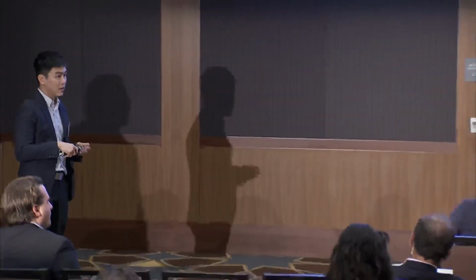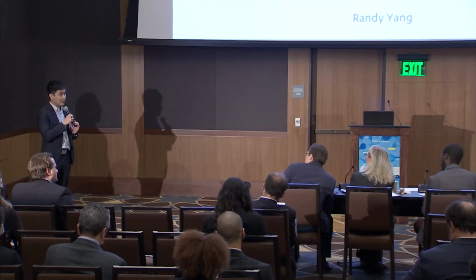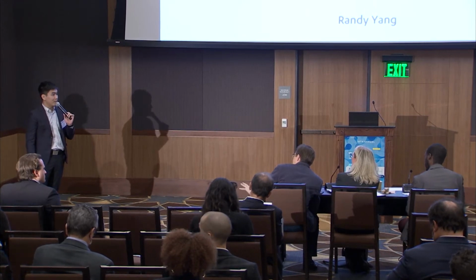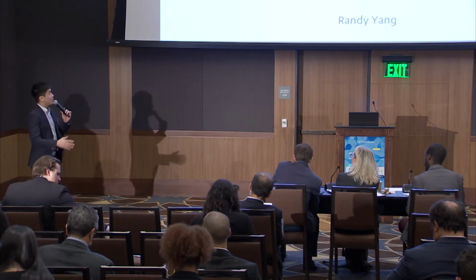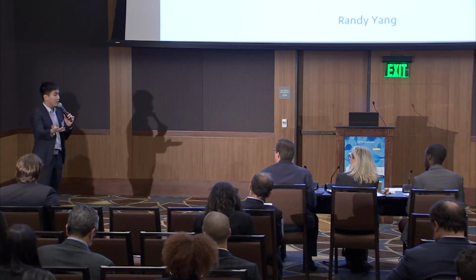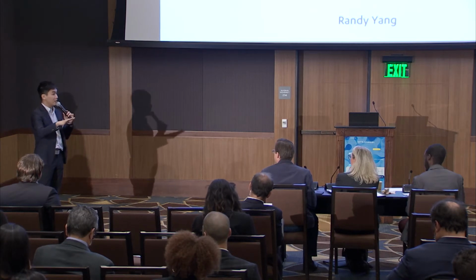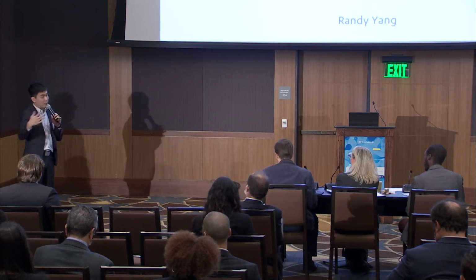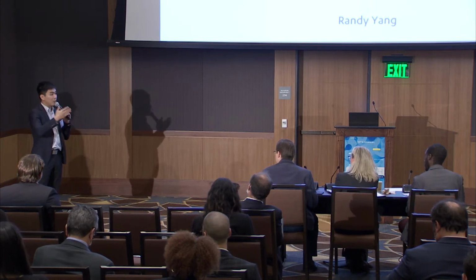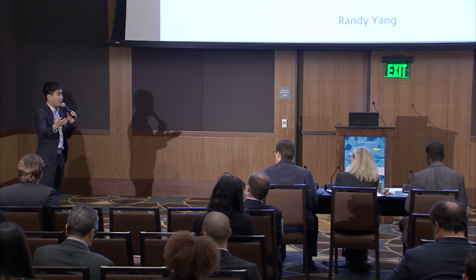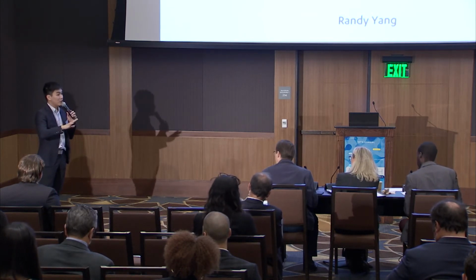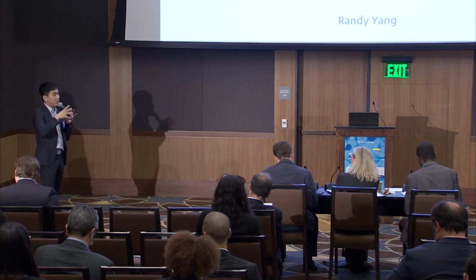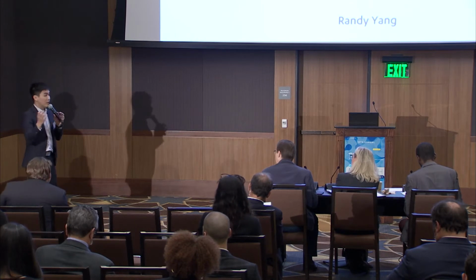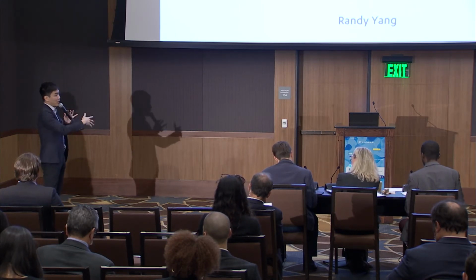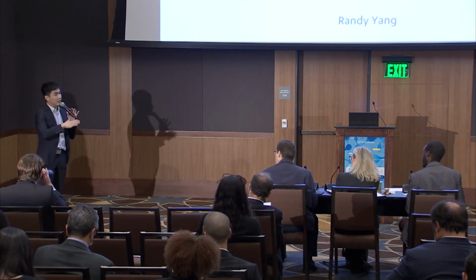Thank you. And for an owner of an MRI machine, what's the cost and the barriers to implementing your coil and replacing it? Right. The standard cost of a brand coil that is now sold by the MRI vendors is around $100,000. If we collaborate with the vendors, we foresee they will take maybe a 20 to 50% margin. So maybe $150,000, which is really marginal to the cost of the whole MRI scanner. But once you bought that, we're keeping the workflow, right? Everything will stay the same, but you put it in, with some software upgrade and hardware integration, and then that's done.